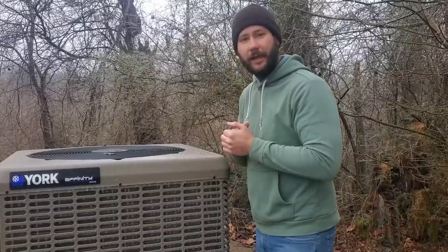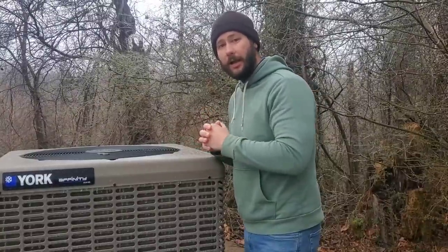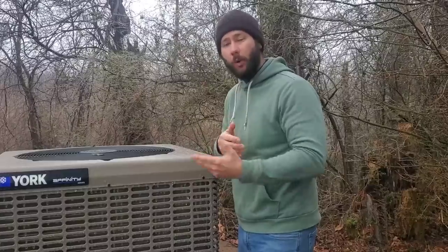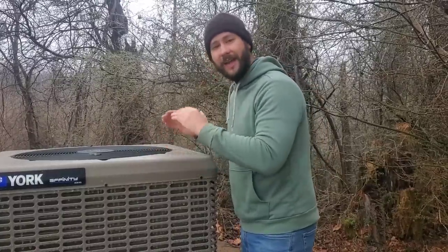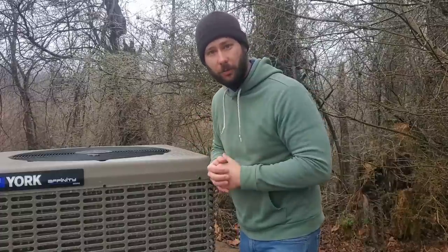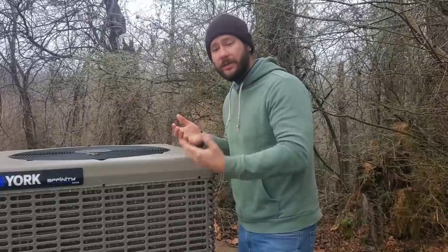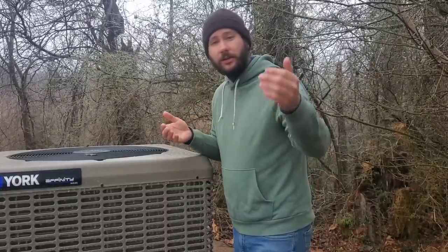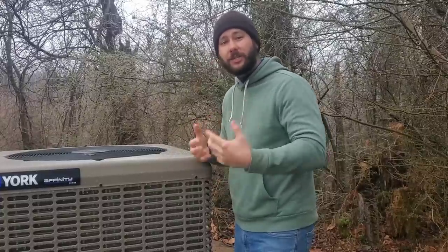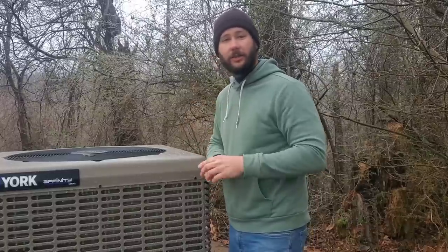We don't want the motor, blades, or outdoor coil damaged because you didn't turn your thermostat to emergency heat and ice fell from your gutters or roof. This is the outdoor equipment trying to gain heat from the outside air — at a certain point the capacity decreases and the load of your structure exceeds the capacity of the equipment. If you have a conventional heat pump it becomes inefficient and needs heat strips. If you have VRF or mini-splits, they're different — they don't need heat strips. You can check out SamsungHVAC.com for VRF technology that heats even at negative temperatures.